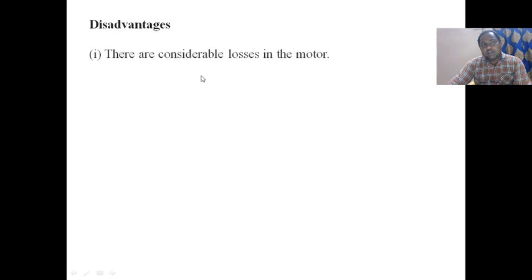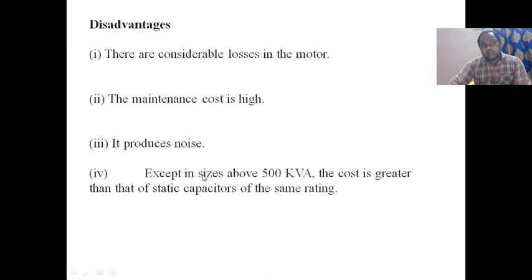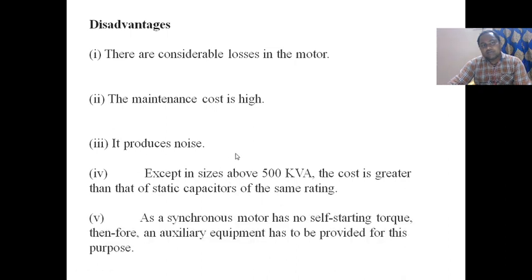Disadvantages: there are considerable losses in the motor, meaning friction and windage losses because this is a rotating machine. The maintenance cost is high. It produces noise because this is a rotating machine. Except in sizes above 500 kVA, the cost is greater than that of a static capacitor of the same rating. As a synchronous motor has no self-starting torque, an auxiliary equipment has to be provided for this purpose.